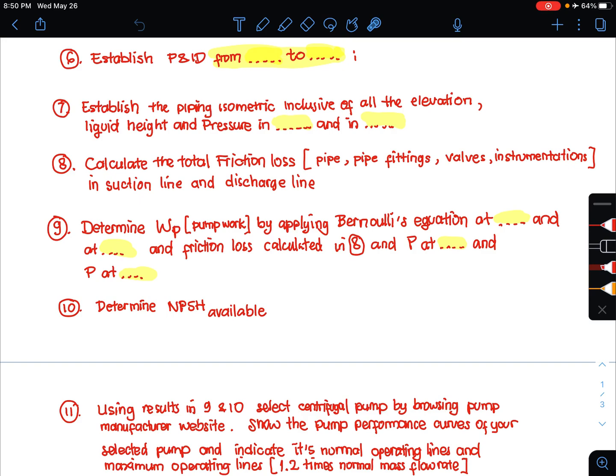The next step is to calculate the total friction loss — in the pipe, in the pipe fittings, in the valves, and in the instrumentation — for both the suction line and the discharge line.